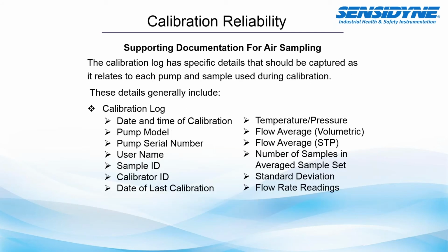The calibration log has specific details that should be captured as it relates to each pump and sample used during calibration. So these details that should be specifically recorded on a calibration log include the date and time of calibration, the pump model, the pump serial number being calibrated, the username, the sample ID, the calibrator ID, the date of last calibration, the ambient temperature and pressure at which you're calibrating, the flow average, which is your volumetric average, if need be, the calculated STP flow average, the number of samples in your averaged sample set, the standard deviation between those samples, which again shows that stability, and then the flow rate readings themselves.